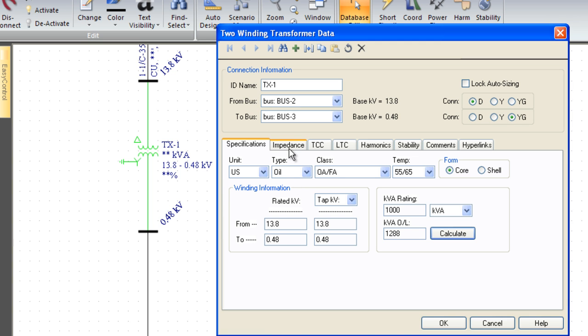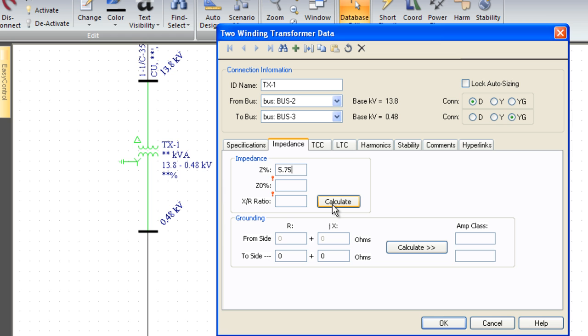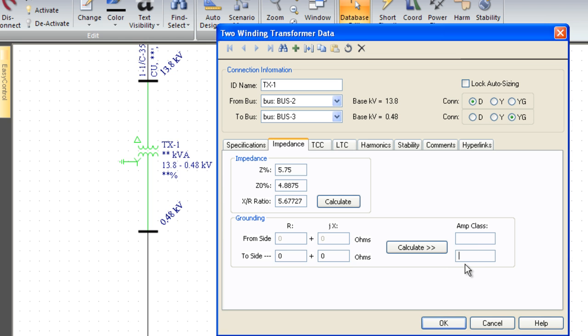Typically there's two tabs for most equipment that we need to fill out data for. The second tab for a transformer is the impedance data. We need to know what that positive sequence impedance data is. It's right on the nameplate, probably something like 5.75 or 6%. You're never going to find the zero sequence or the X over R ratio for a transformer on the nameplate. We provide a calculate button that will calculate the zero sequence based on a typical core type transformer design and the X over R ratio based on ANSI standards.